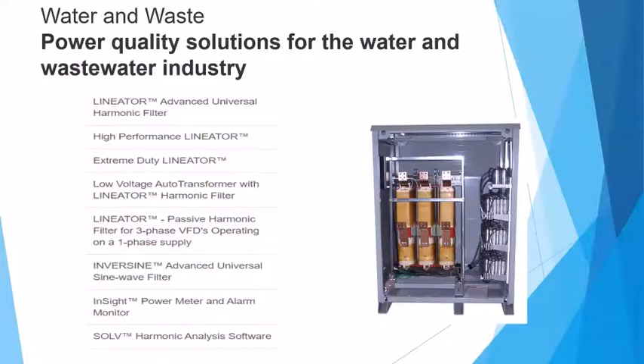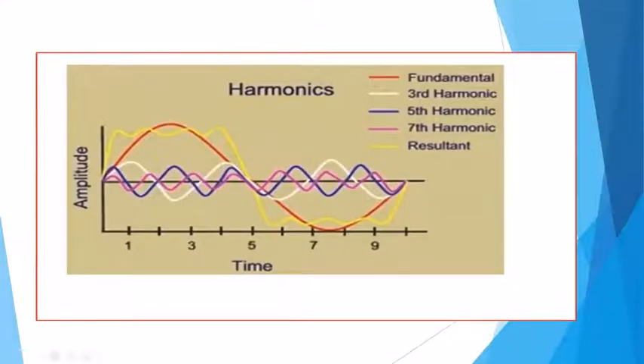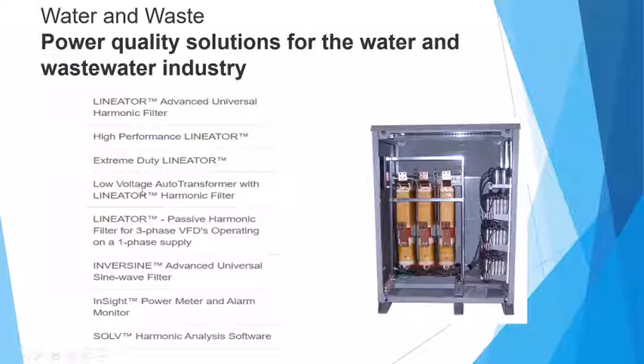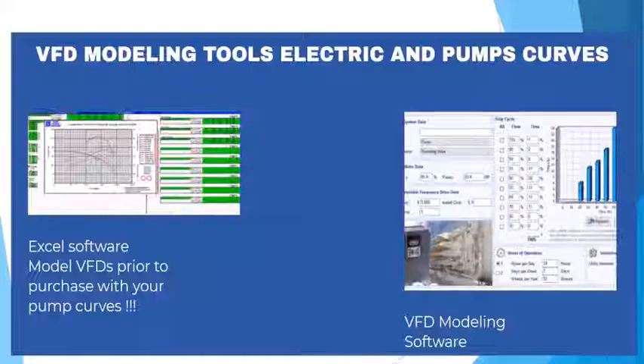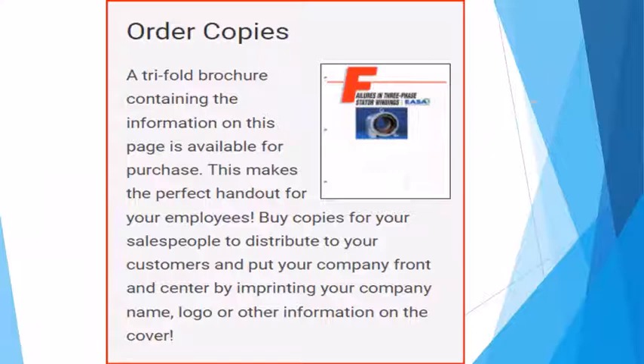Why things are, because almost 90% of the people out there that are using standard amp meters and voltmeters never see this. They don't see anything about the harmonics, don't see anything about the noise, and oh well, just put a filter on it, put a filter on the output. Yeah, but then all of a sudden you've got all these extra losses. So I like to keep it simple and make the system as easy as possible.